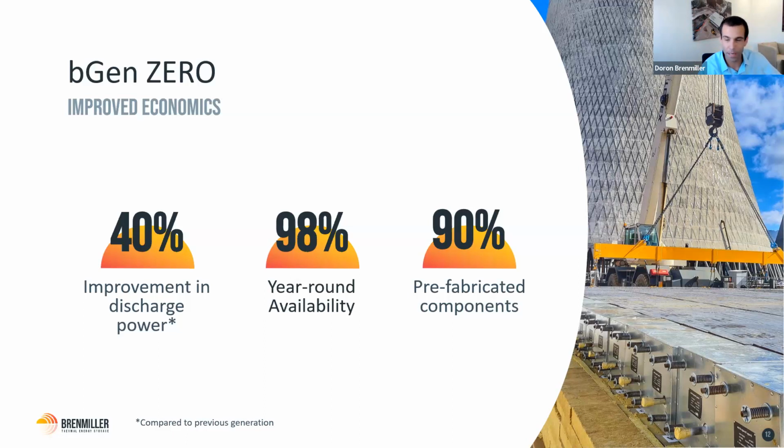And a couple of other parameters we really worked hard on is the availability. So customers depending on such solutions want to have high availability. They need this to service their hospitals, their manufacturing lines. They don't want something where one component breaks and the entire system stands still until it's fixed. Because we have multiple parts, the system is built in a very redundant way, many heaters, many modules. A few items like electrical heaters can fail, and we can continue to work very nicely and just stop for scheduled maintenance. So this allows us to get to this very high number of availability.